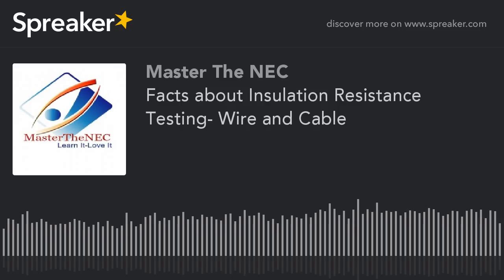So insulated conductor to insulated conductor, unless you're looking for some signal that it's a totally damaged wire, I still encourage the test. But what I want to guard people against is the values they get when they check an insulated conductor to an insulated conductor in a cable. Because if I have an MC cable, I have the individual conductors, and based on UL 1569, you actually have a binder material that wraps the conductors and separates it between that and the armor.